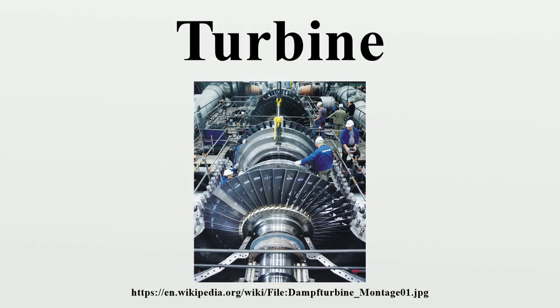For compressible working fluids, multiple turbine stages are usually used to harness the expanding gas efficiently. Newton's third law describes the transfer of energy for reaction turbines. In the case of steam turbines, such as would be used for marine applications or for land-based electricity generation, a Parsons-type reaction turbine would require approximately double the number of blade rows as a de Laval-type impulse turbine, for the same degree of thermal energy conversion.